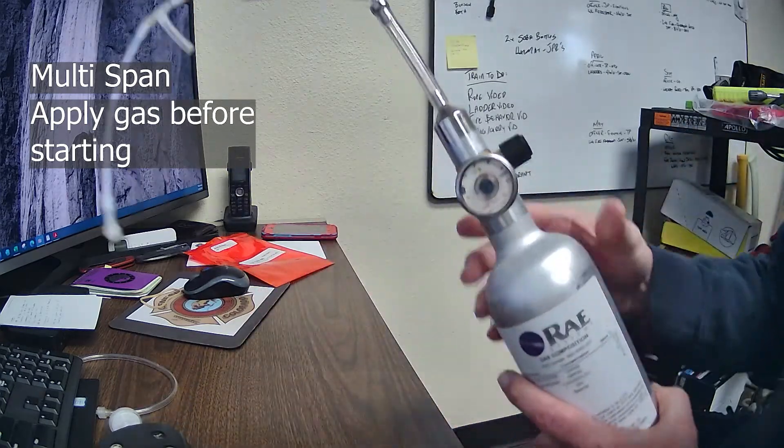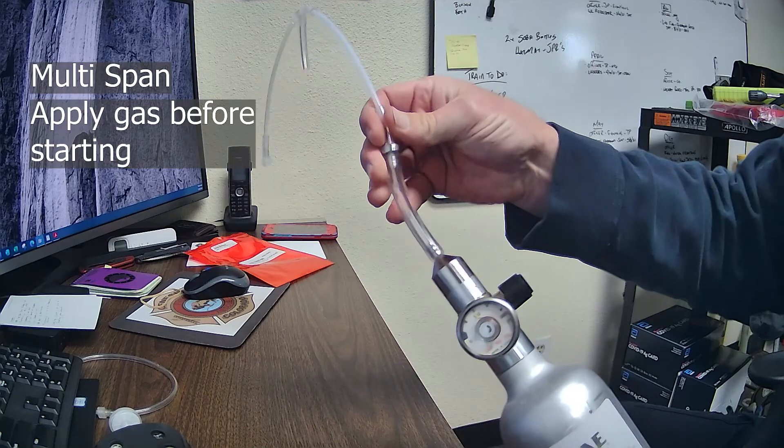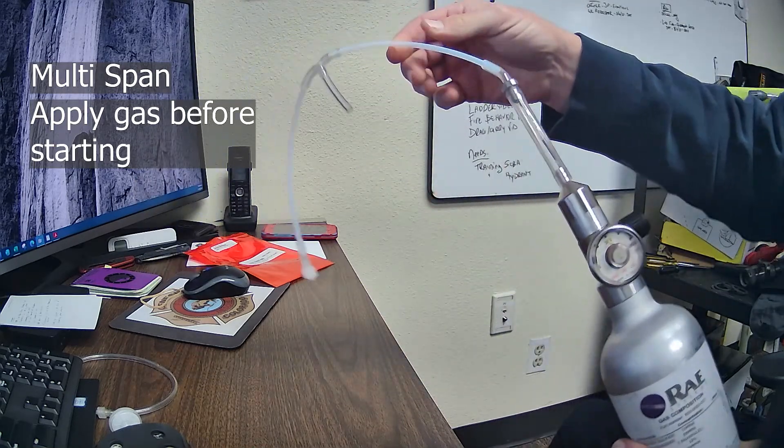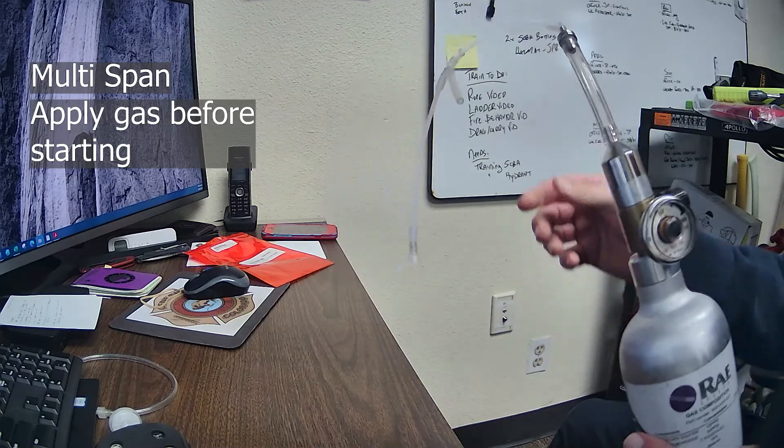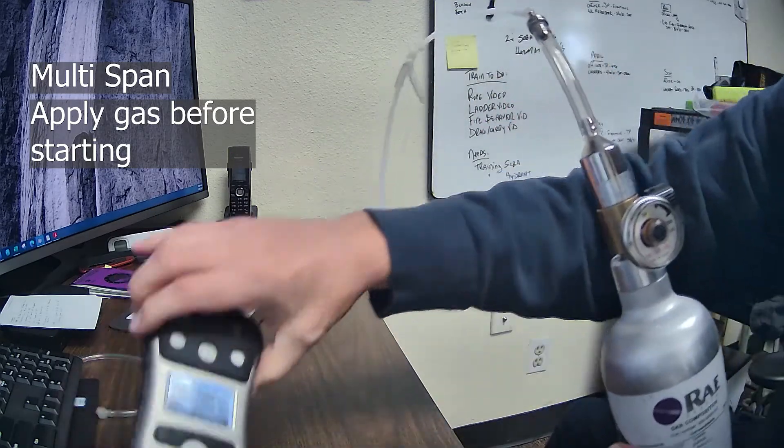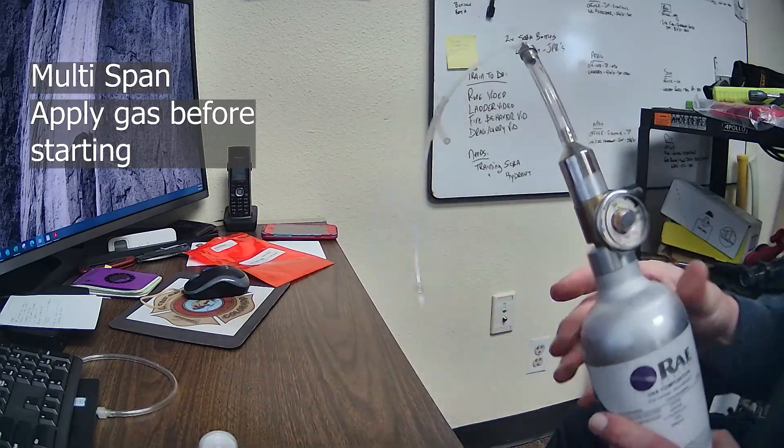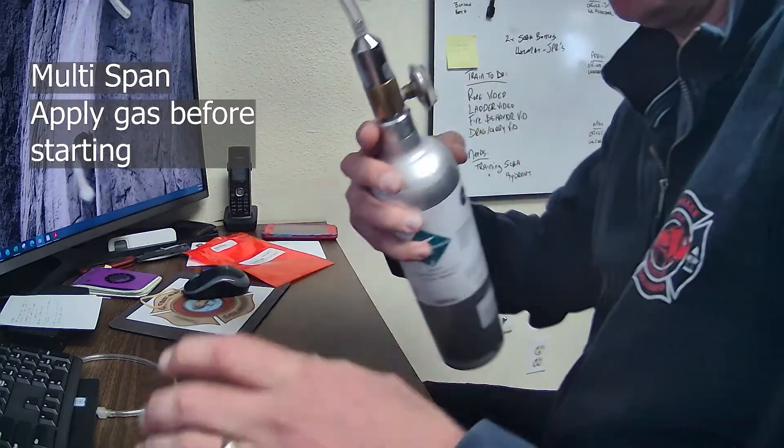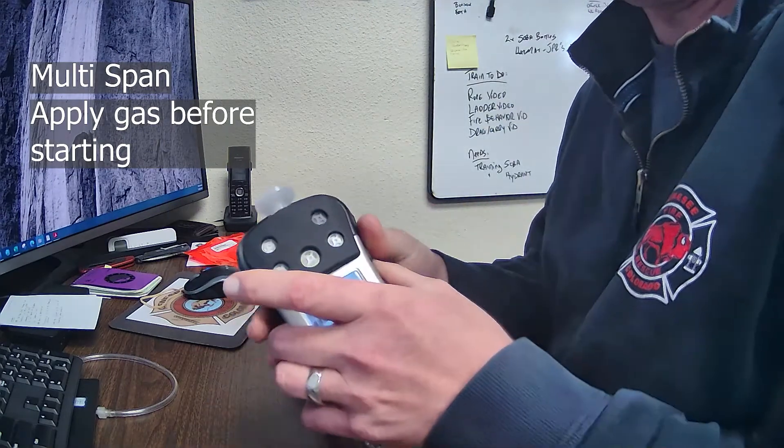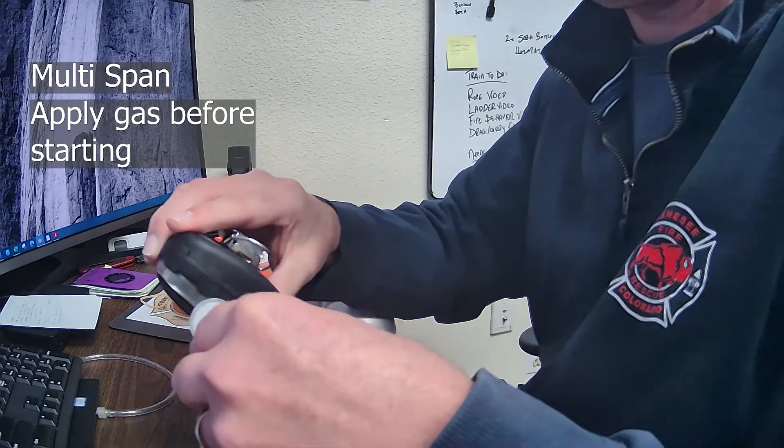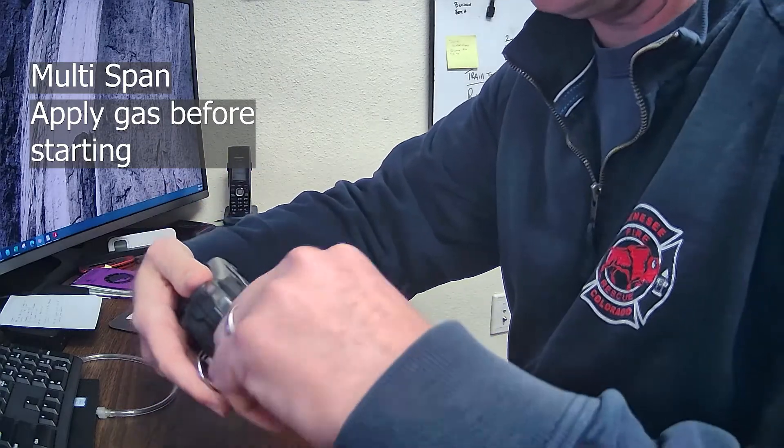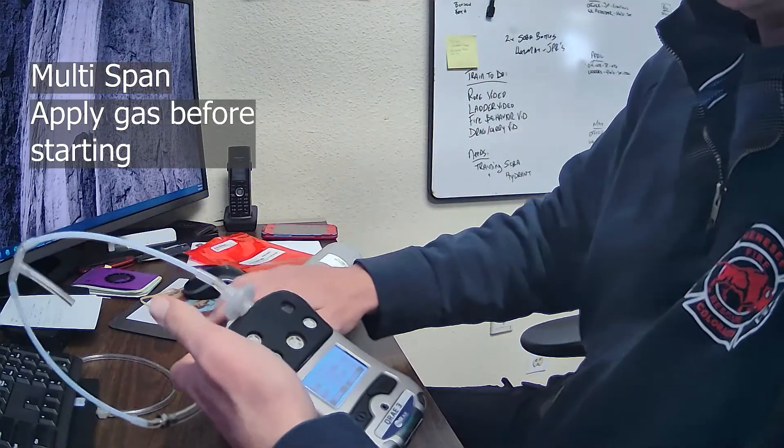So take a second. This is how it looks. This is how it should look like. A little adapter that goes to a smaller T-hose, and this, we need to do this for these QRAE 3s, because if we don't, this liter per minute will blow up the pump on this three milliliter per minute pump. So, put this on there, so you don't break this. We blow up the pump, and he said it's something like $400 to repair.